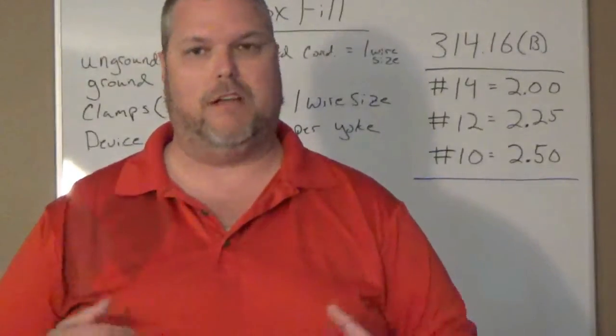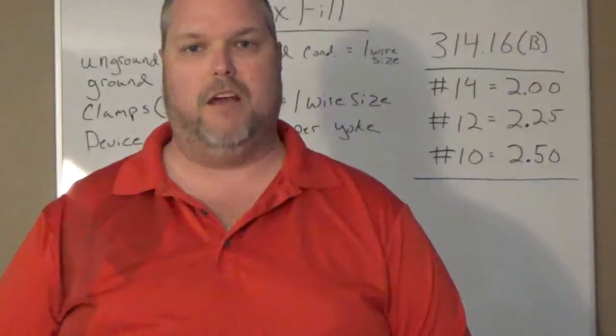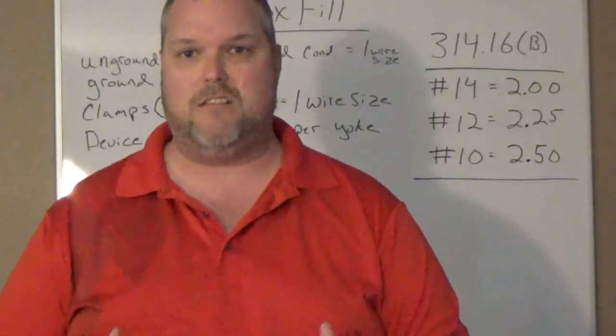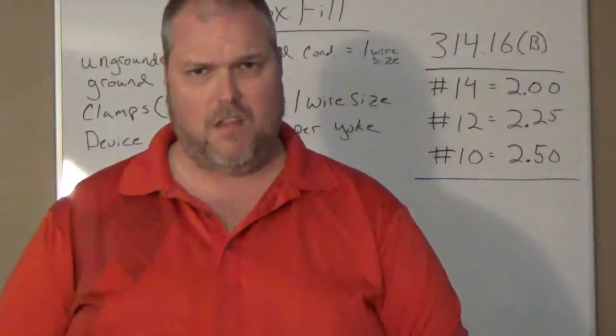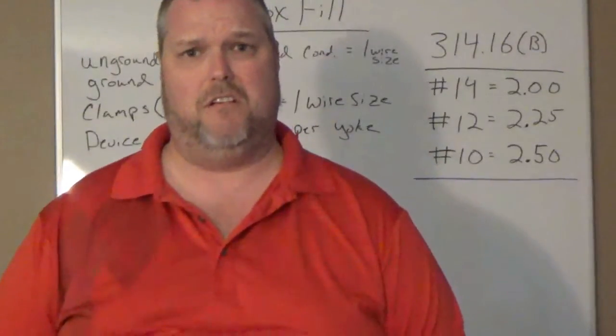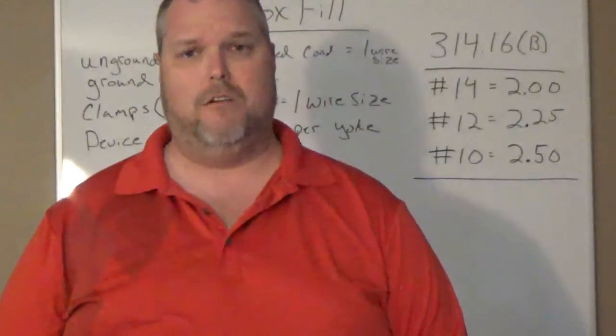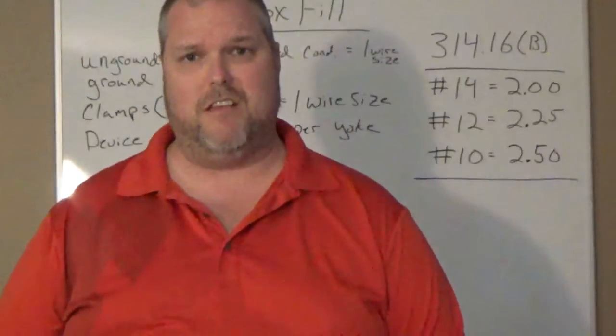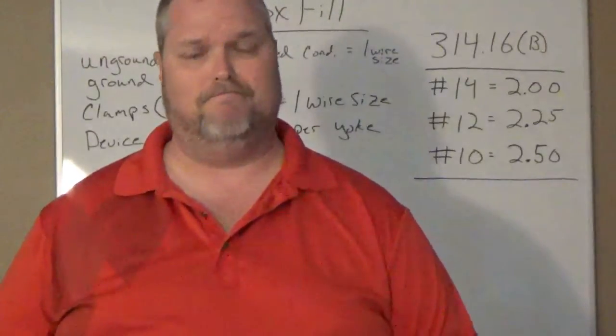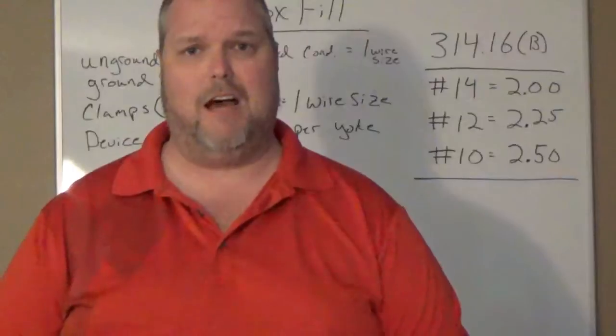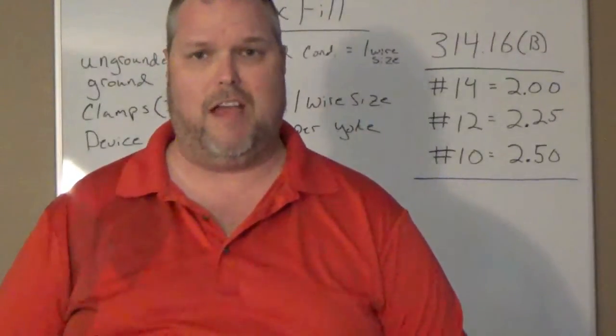Fixture yokes. You got to know if you're putting a fixture yoke in for a lighting device, a hickey, something of that nature, that's also calculated into our box fill. Wire nuts are really not considered space in our box fill calculation. Really not understanding why because it still is in there, but we basically size it off the wire and they have already gone through many times looking at box fill calculation to figure out exactly what's good and they haven't found anything.